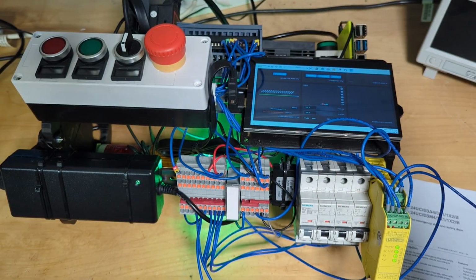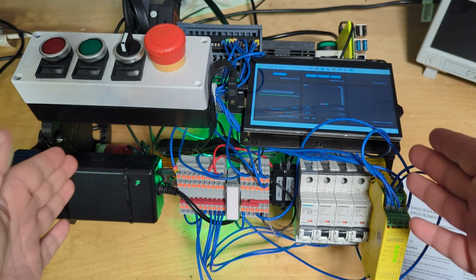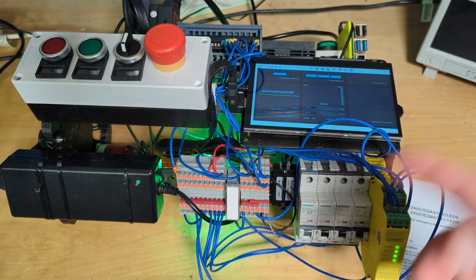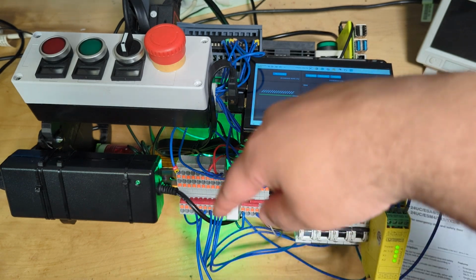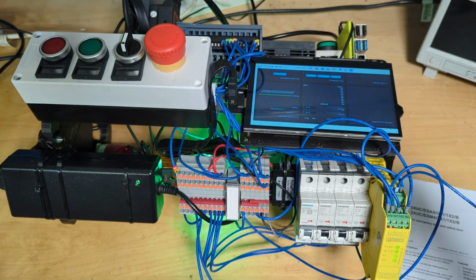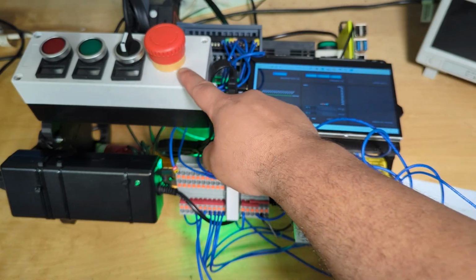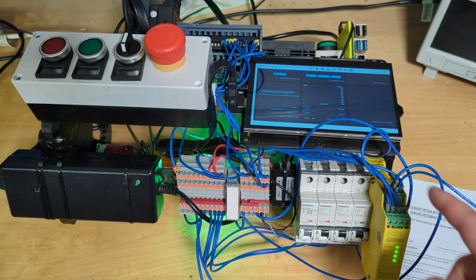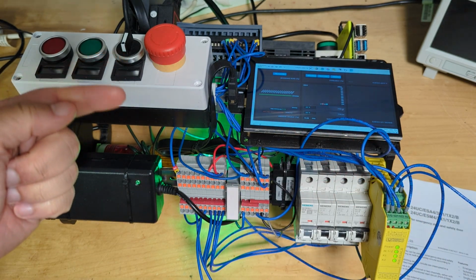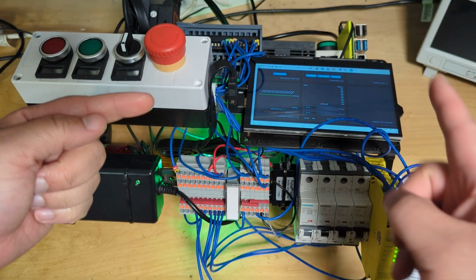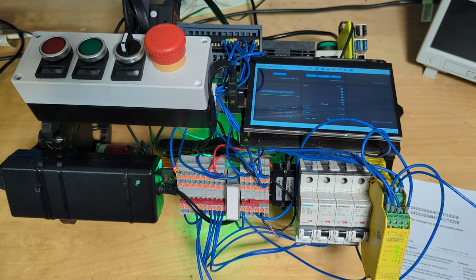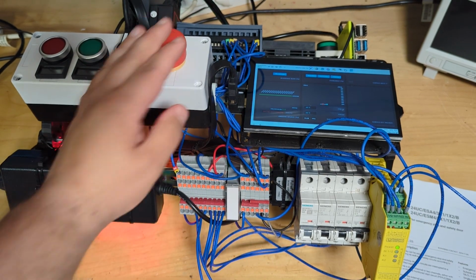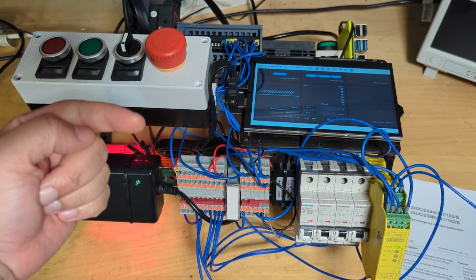It's how it used to be. If you imagine this is a control panel and you had a massive machine, let's say you had to walk around the machine, it was 100 meters around it, you might have 5, 6, 7, 8 e-stops all daisy chained, one to one to one to one. Previously it used to be power incoming and then e-stop going out to your output devices. So when they hit the e-stop, they would be interrupting the power coming in.